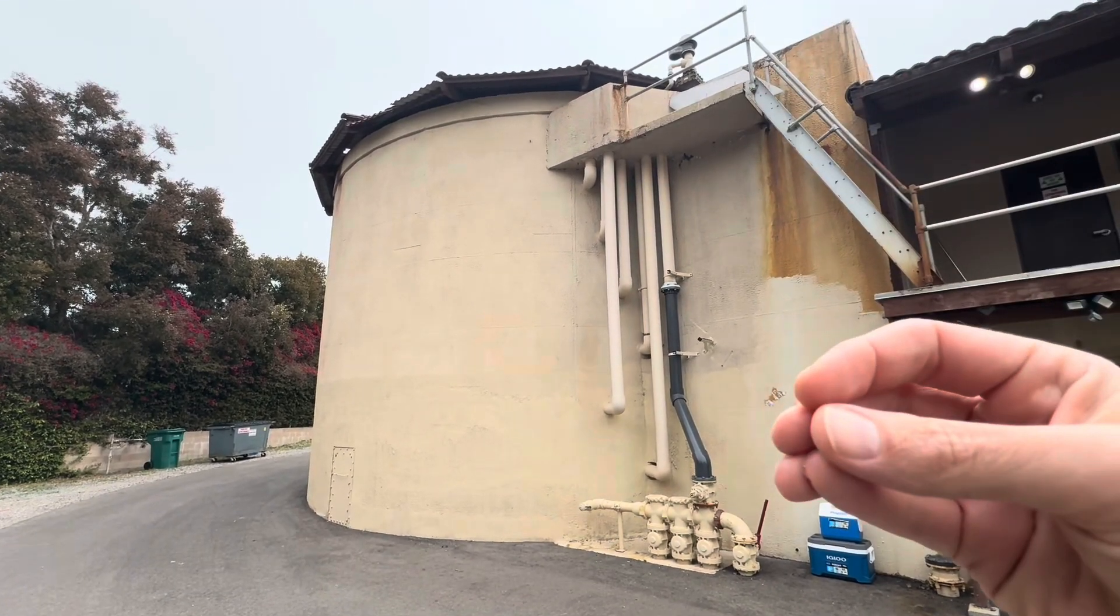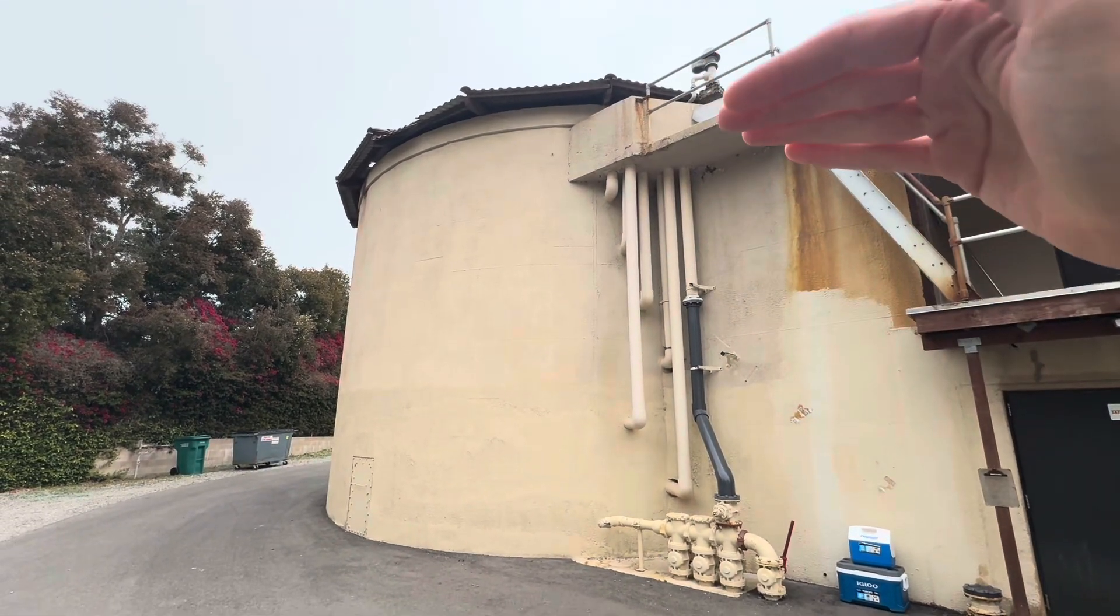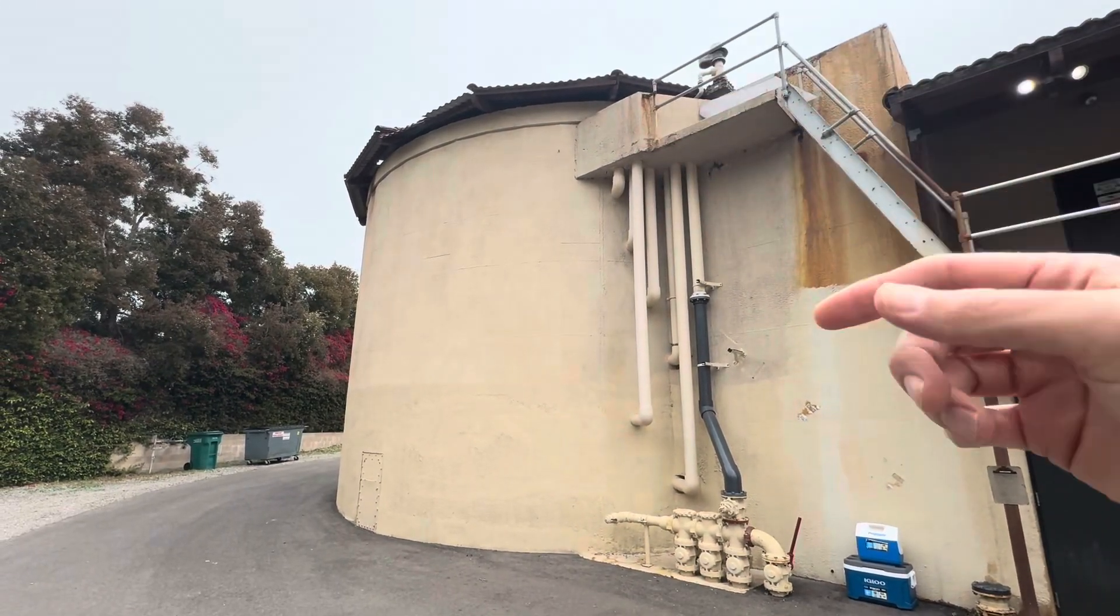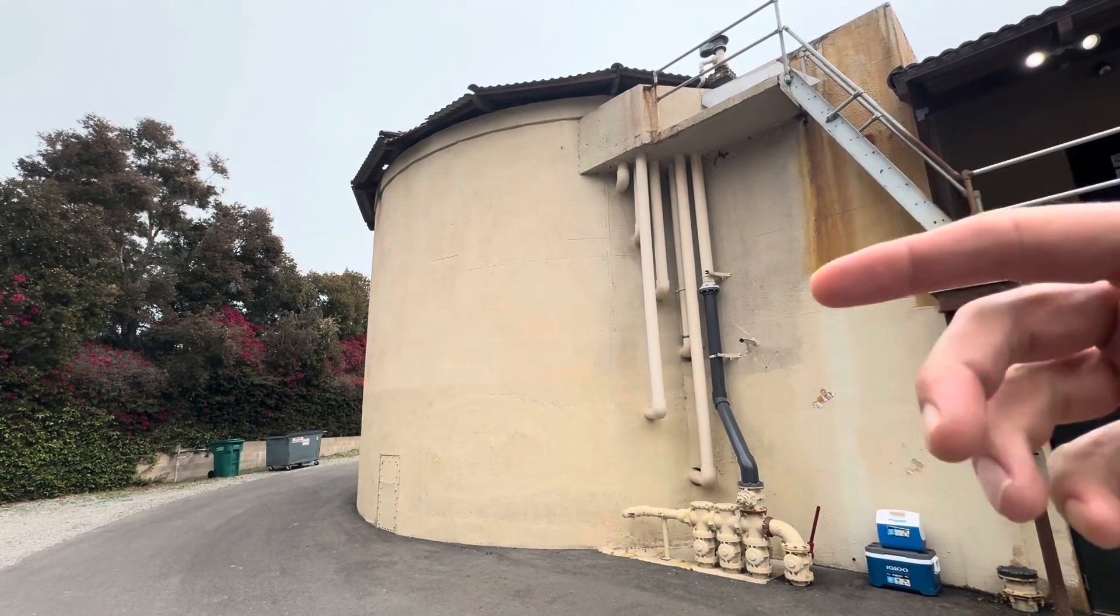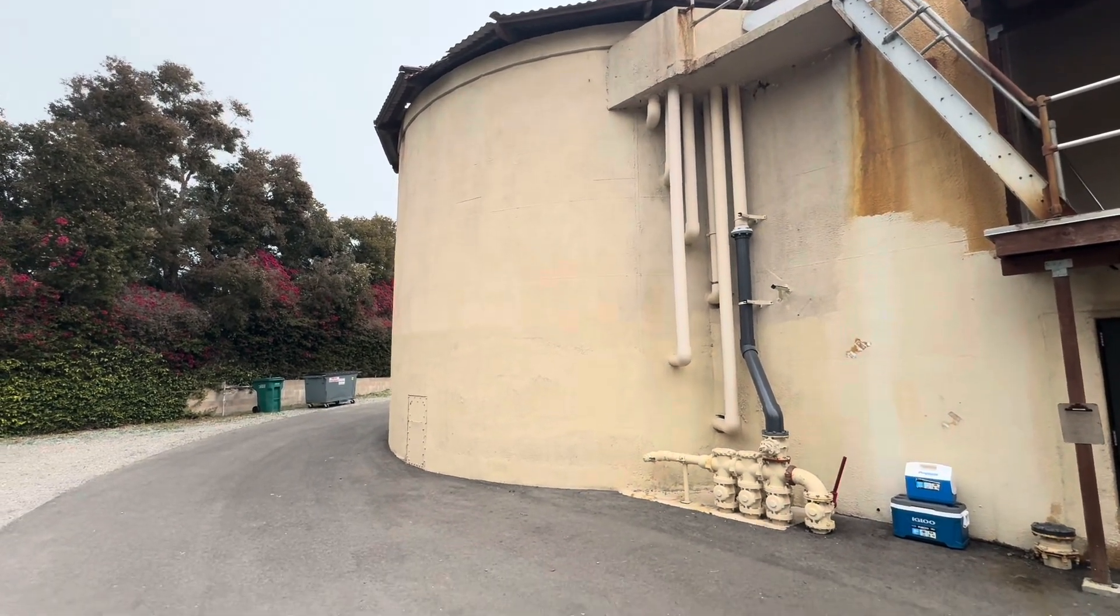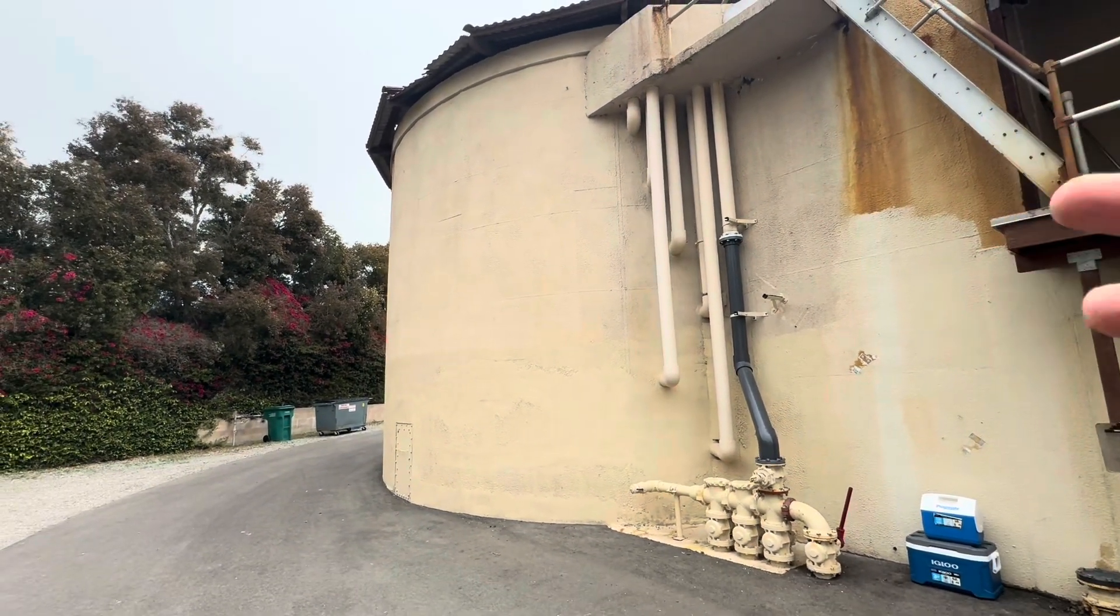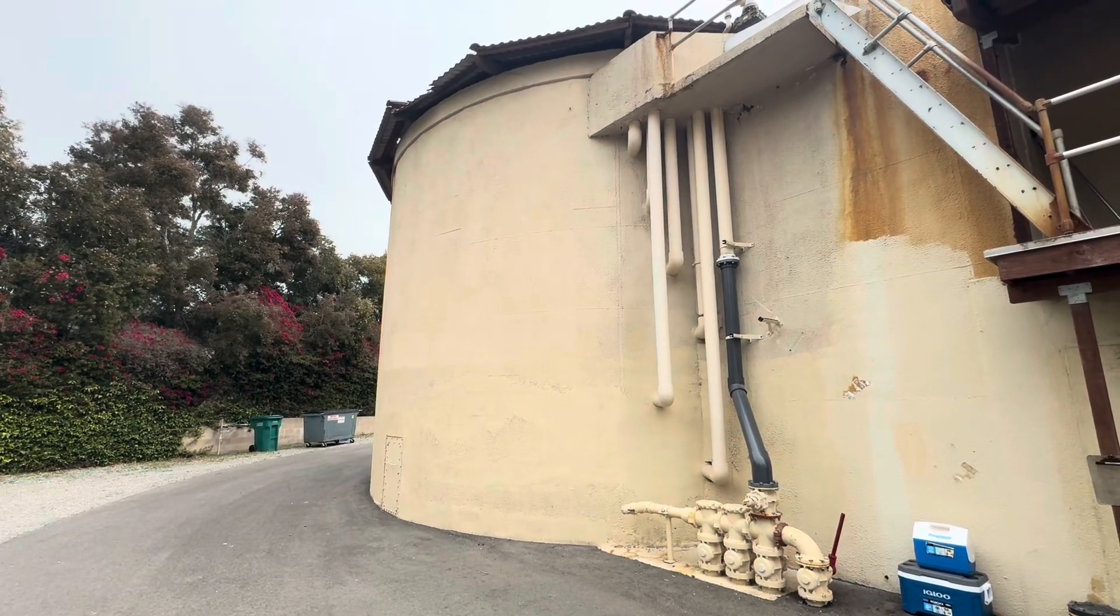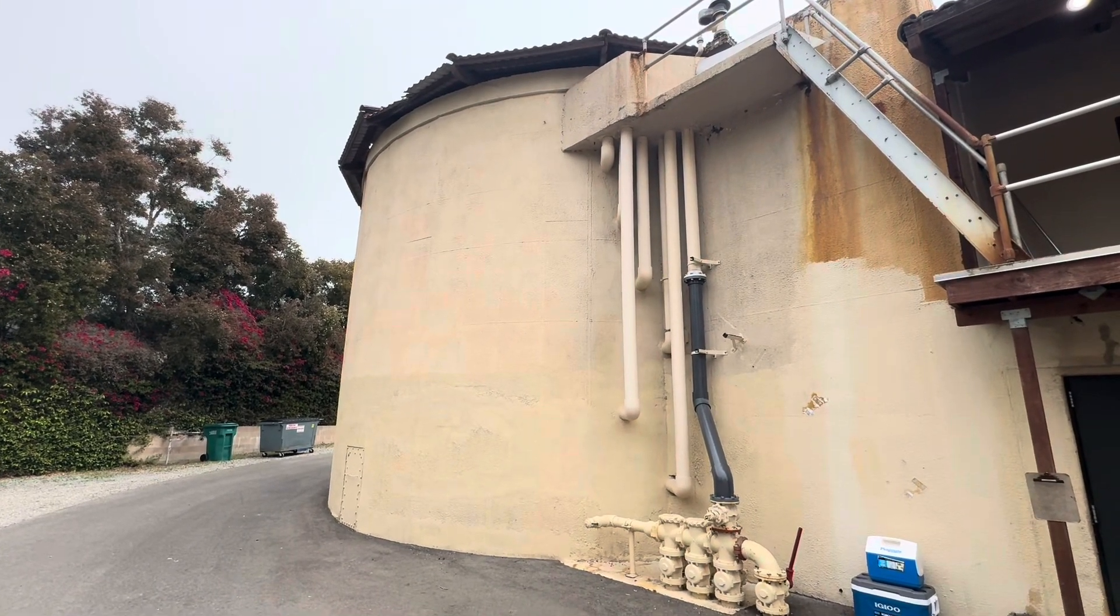And also something you should know is something called a thief hole. And that is a place where you take a sample. I have a terracotta roof. It's a steel roof. It was a steel ceiling with a terracotta roof. I'm not climbing on that roof and breaking those tiles. So what I do is there's rings up in that area. I can adjust them and pull supernatants. I can find my scum layer and I can pull samples off different levels to see exactly where the sludge is, how well digested it looks. So let's go to the whiteboard. I don't want to climb up and down, give you a big tour of this digester since it is an older one. But what we're going to do now is go over to the whiteboard and really hammer home, process control, things you need to know about and some other test materials. Let's go over there.